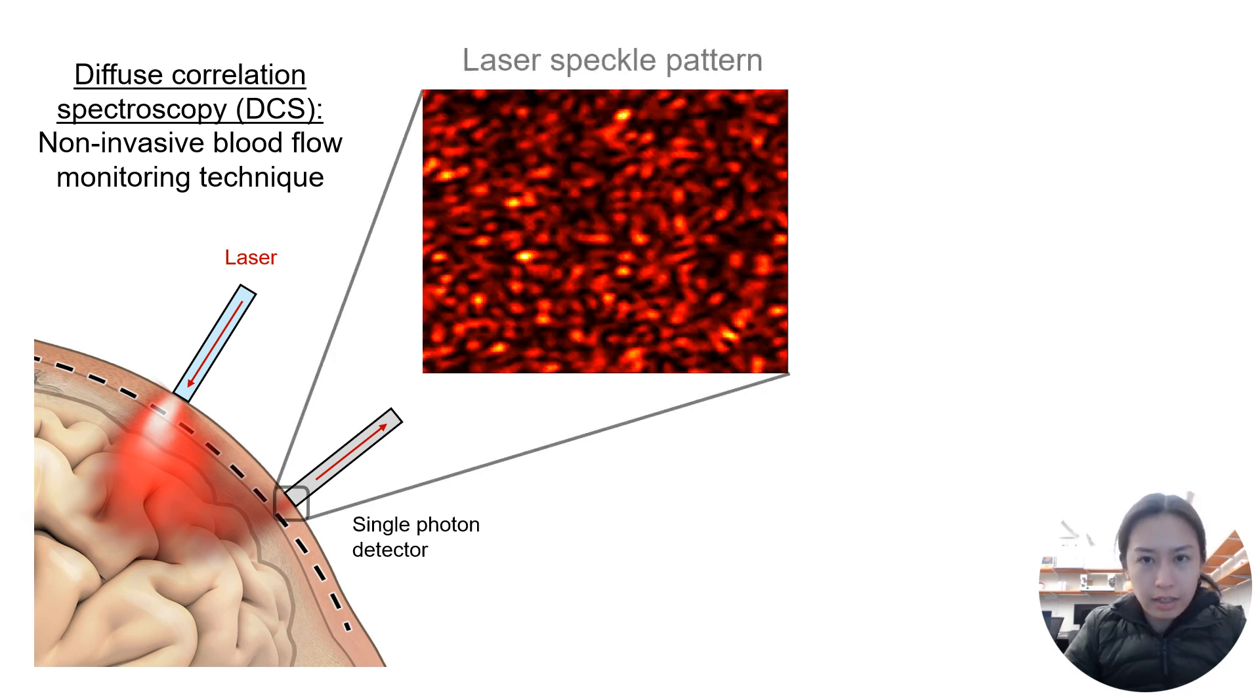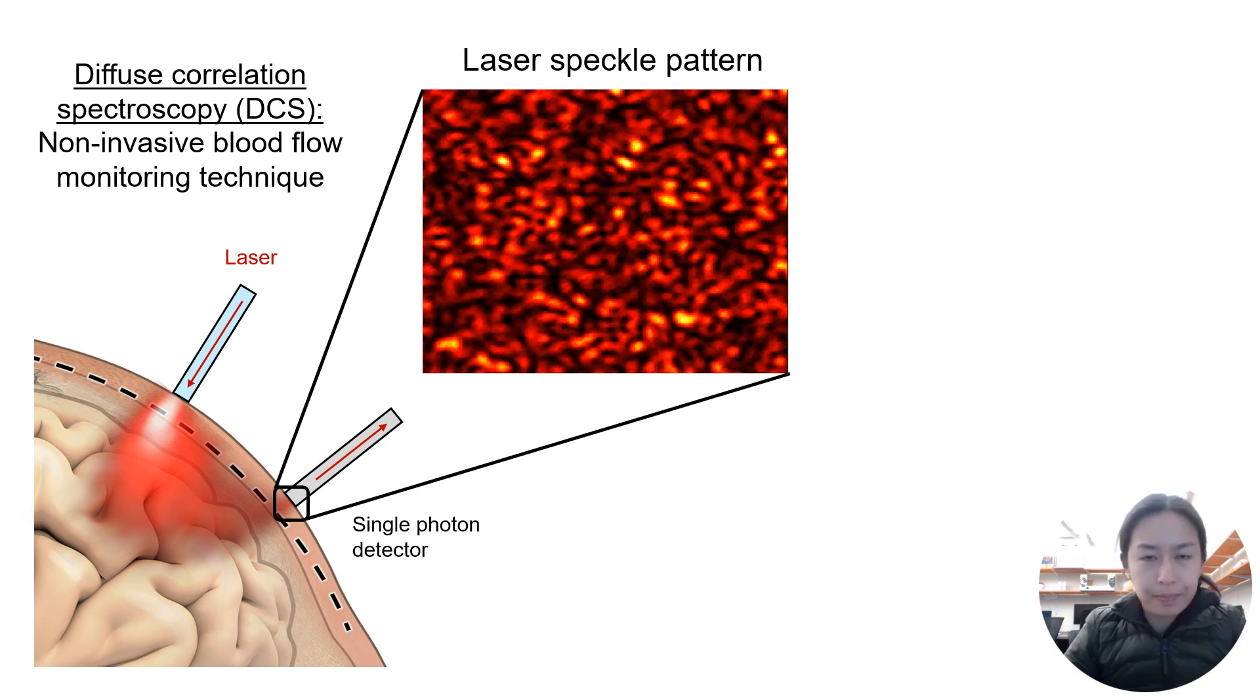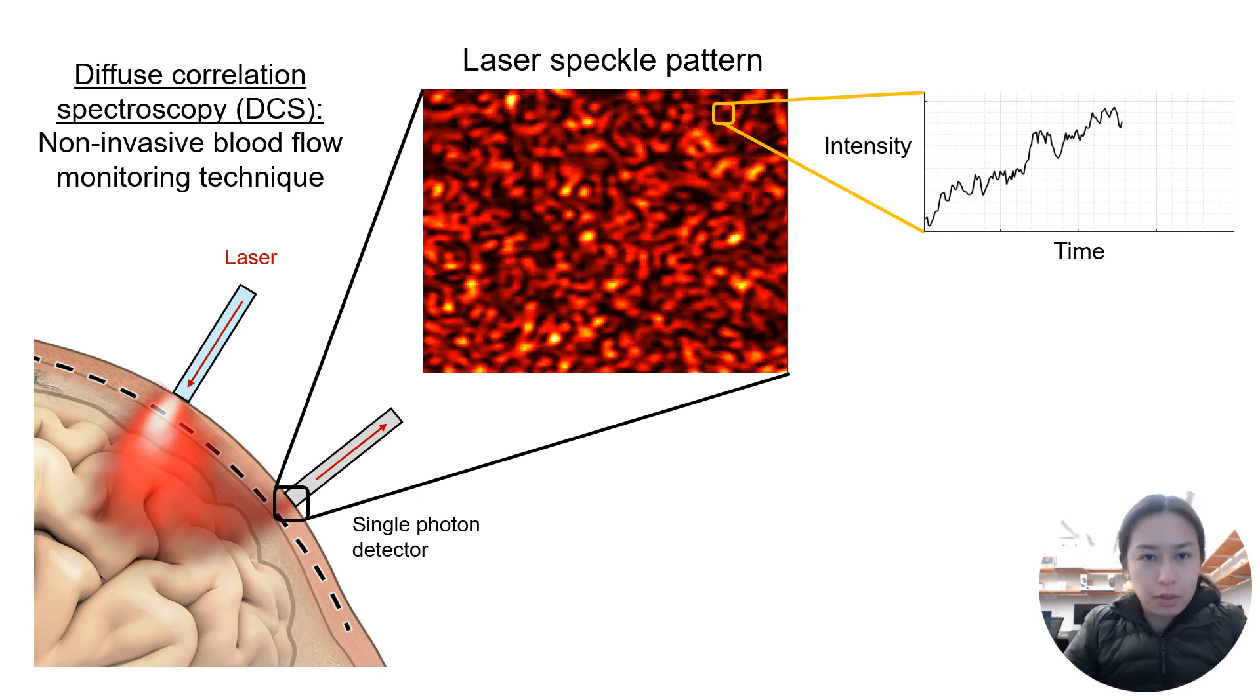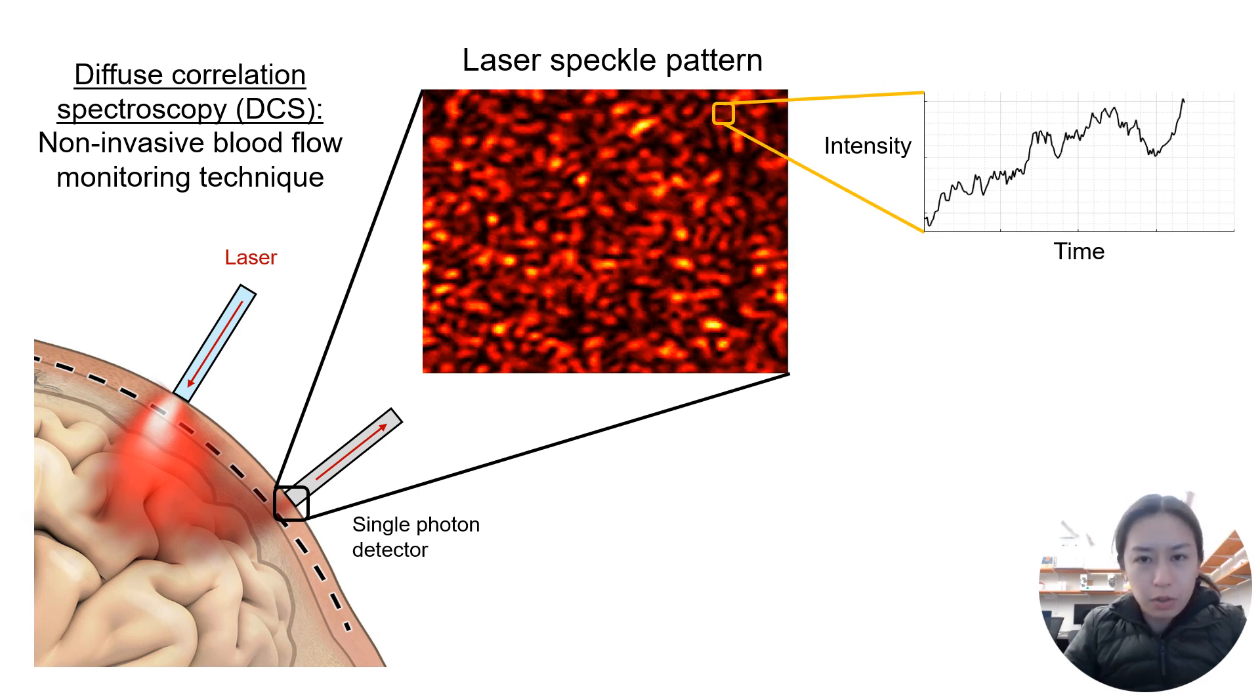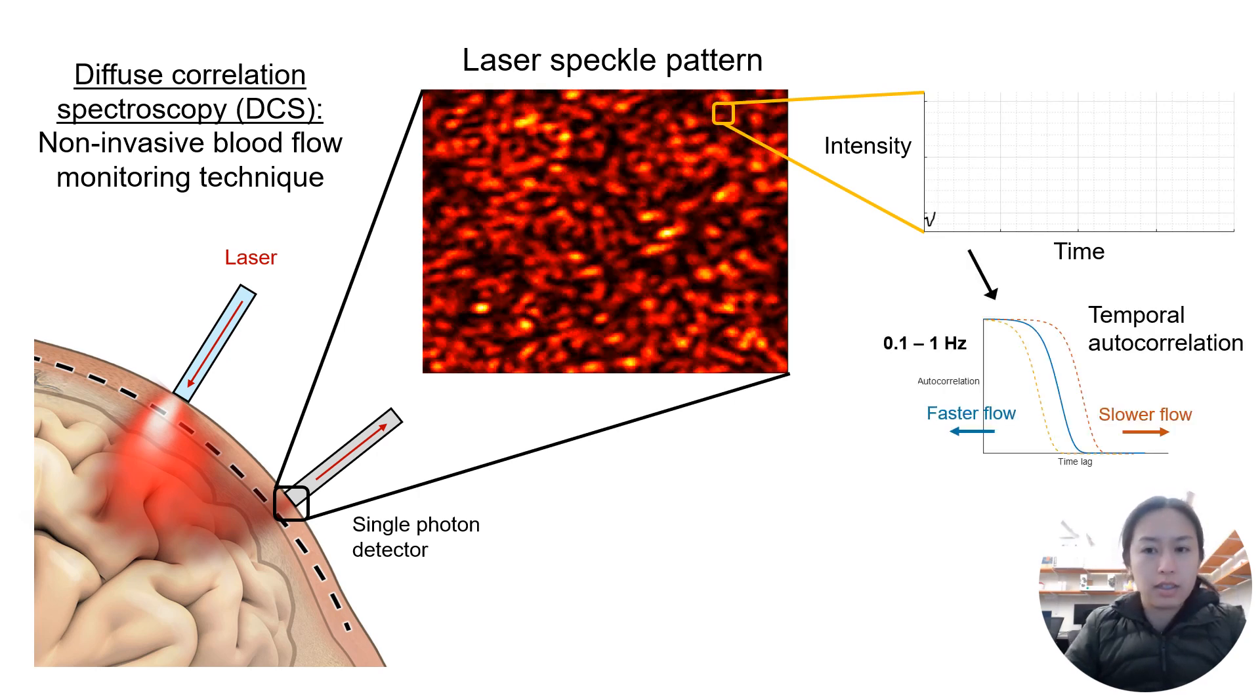DCS is an optical technology used to measure blood flow noninvasively. A long coherence laser is used to deliver light into the head and the laser speckle pattern is detected a few centimeters away. One to several of these speckles are sampled with a single photon detector and the temporal autocorrelation of the detected light intensity is taken.